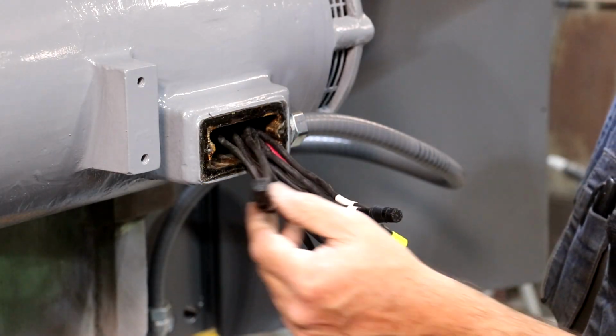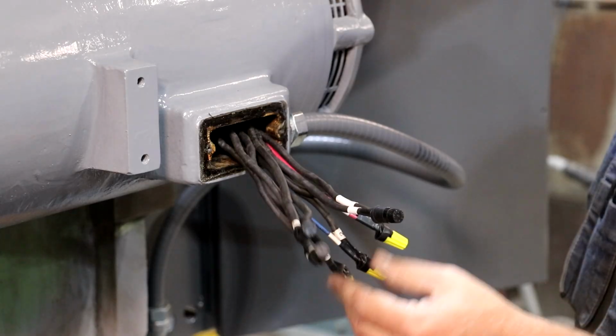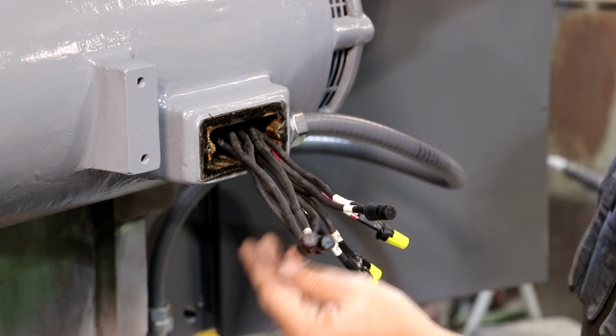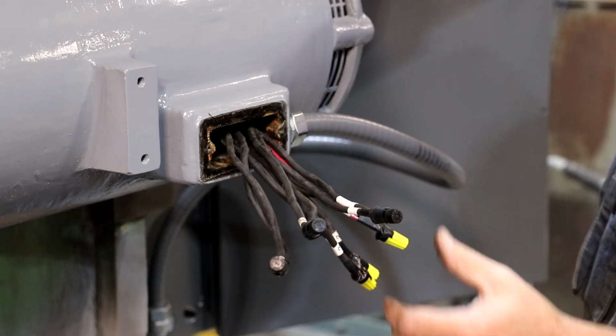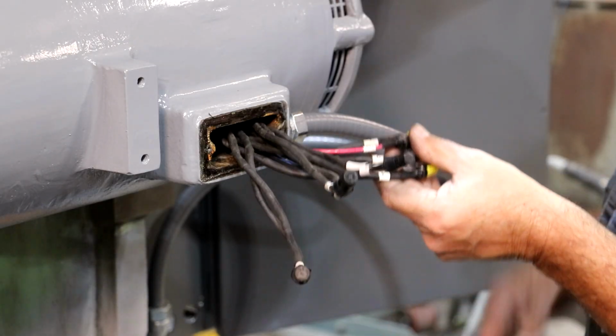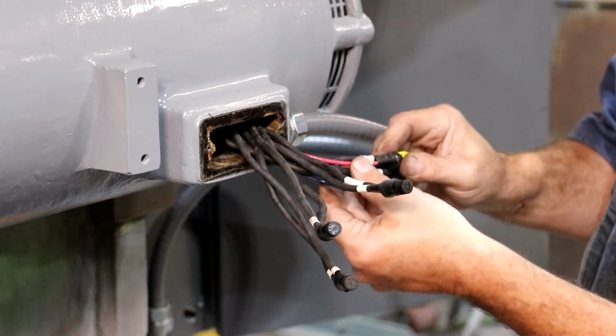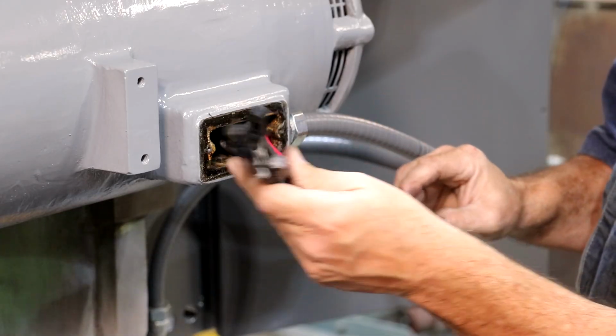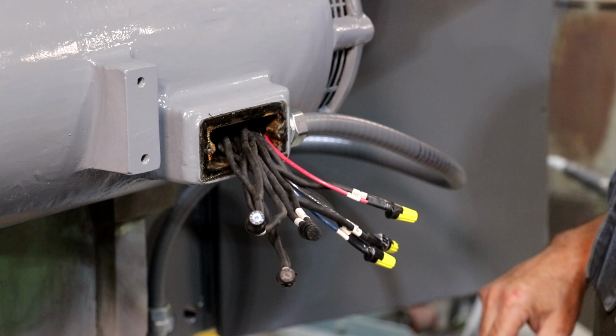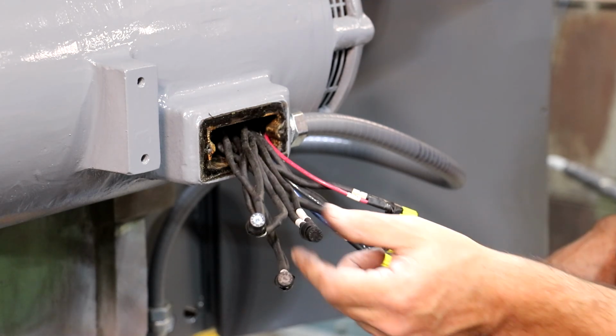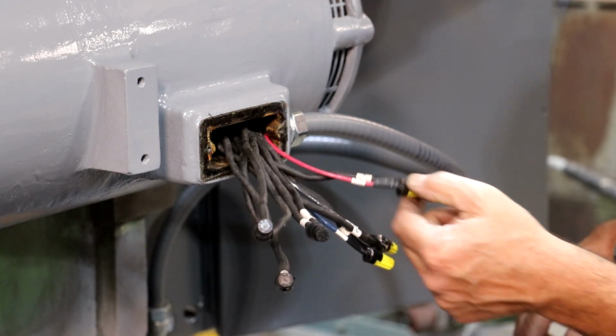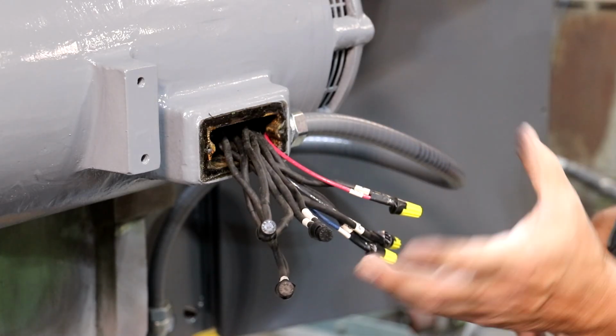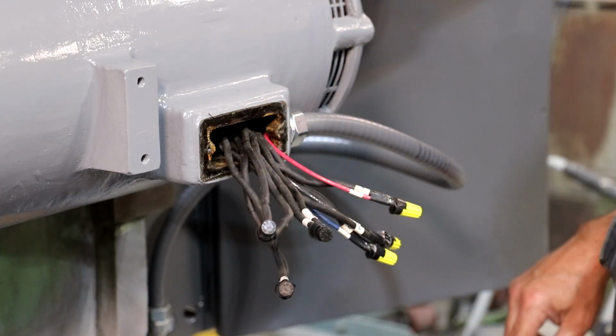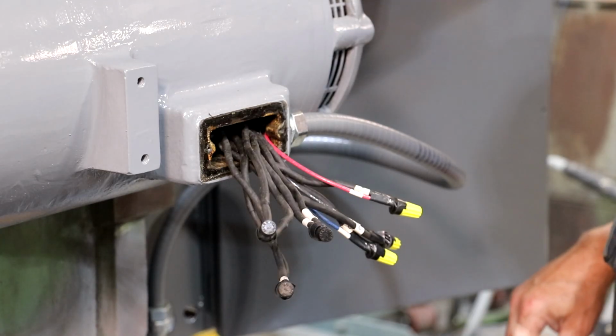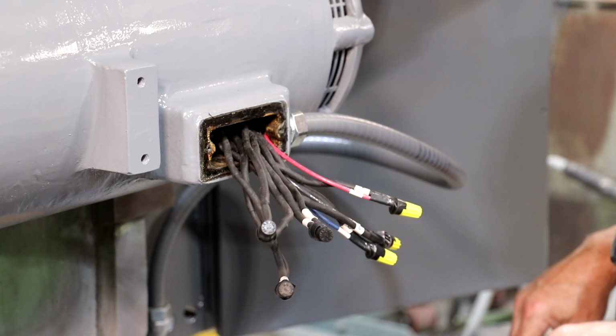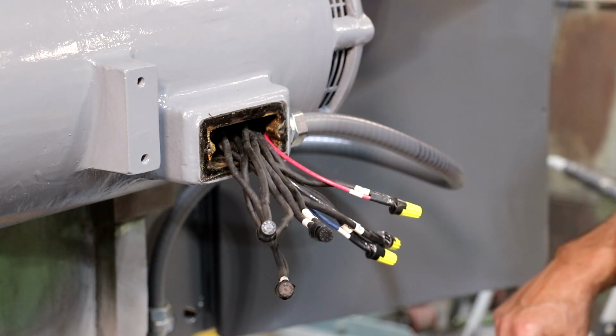Well, this electrical work is always kind of slow, but we got this done. I got all my wires with new shrink wrap on them, so we shouldn't have any wires shorting out in there. I've gone ahead and brought my line wires in - that's the blue, black, and red wire here. These leads are just tied together in the motor, and since I didn't have enough of the fancy little clamps, I just used some regular wire nuts on these three. I'm going to put all this back up inside the pecker head and seal her up, and we'll try this motor out once we get the switch wired in. But this should be ready to go.